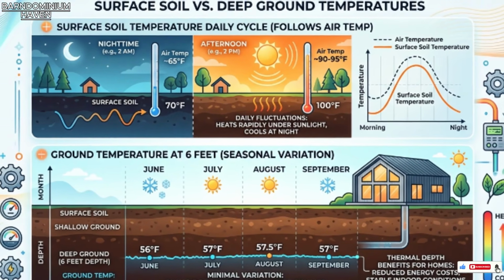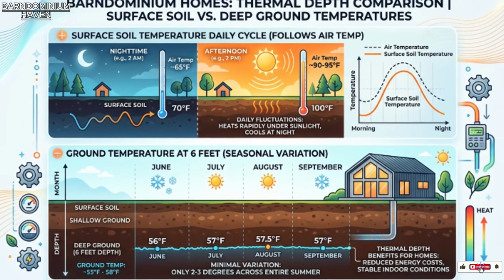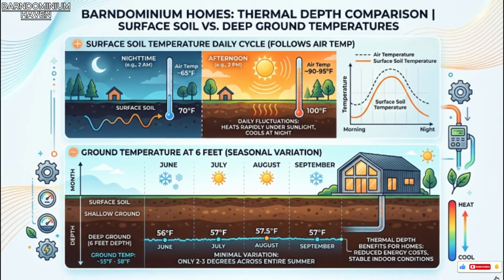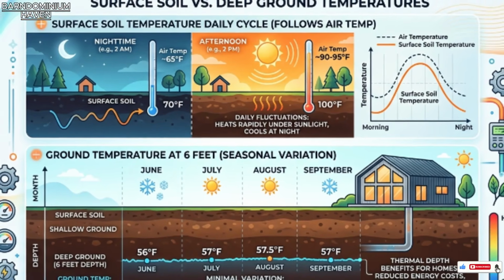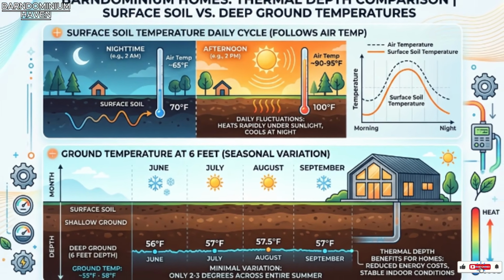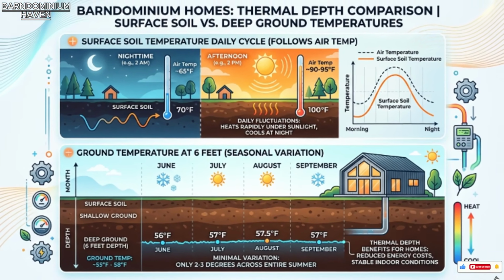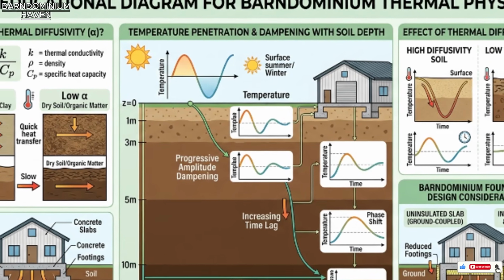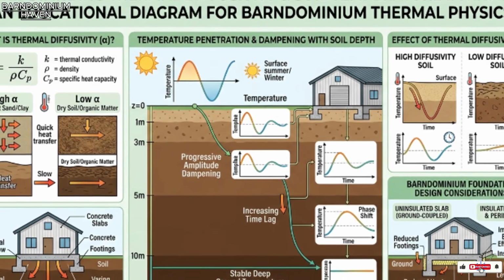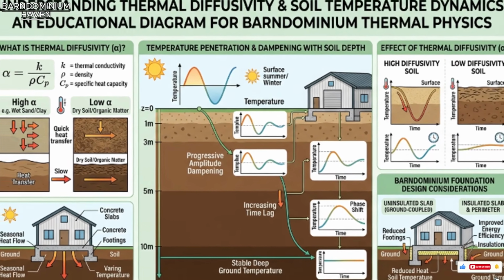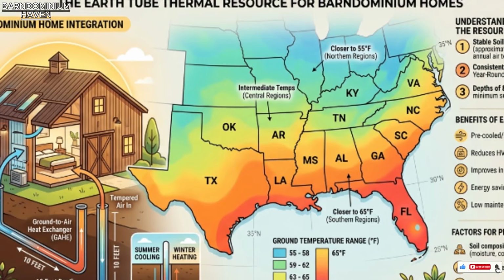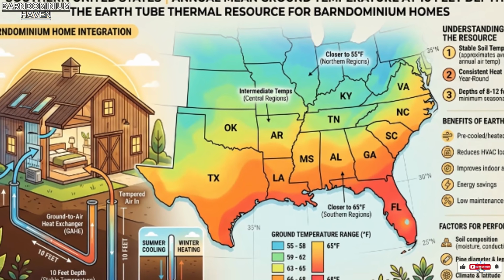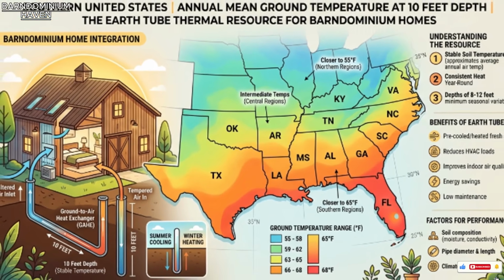The temperature varies with the season but not with the day. At 6 feet of depth, the seasonal cycle is dampened. The temperature varies slightly between summer and winter, but that variation is measured in single degrees, not in the 50 to 90 degree swings that surface air experiences across a Texas or Oklahoma summer. At 10 feet of depth, the temperature is essentially constant year-round.